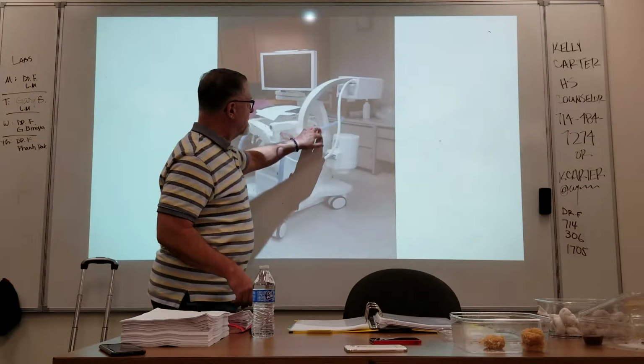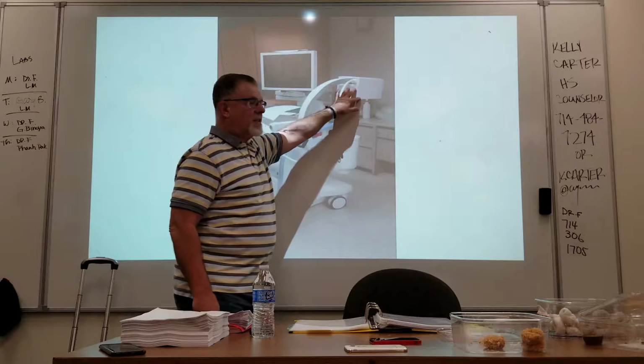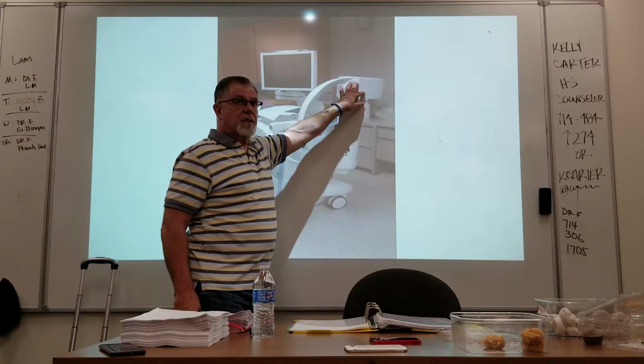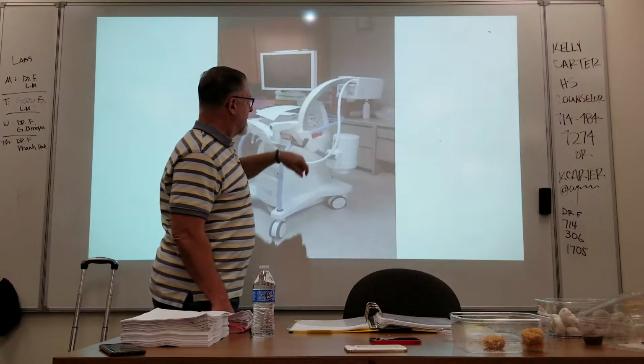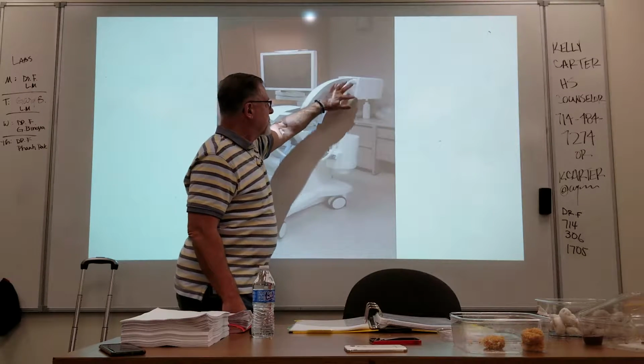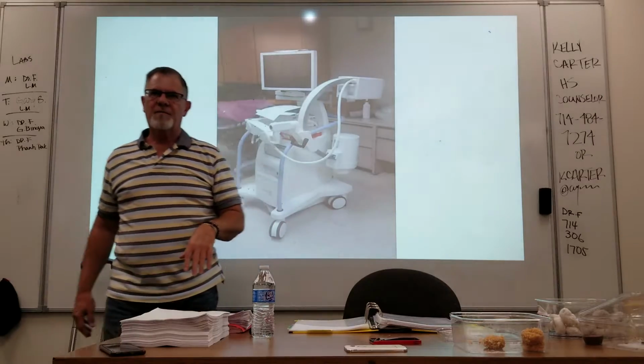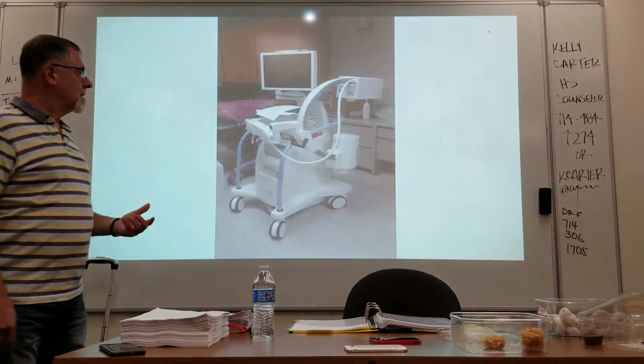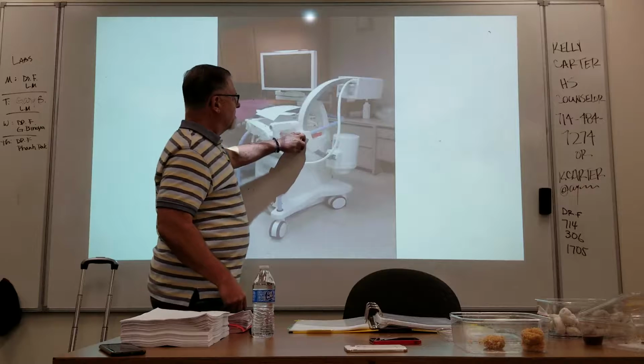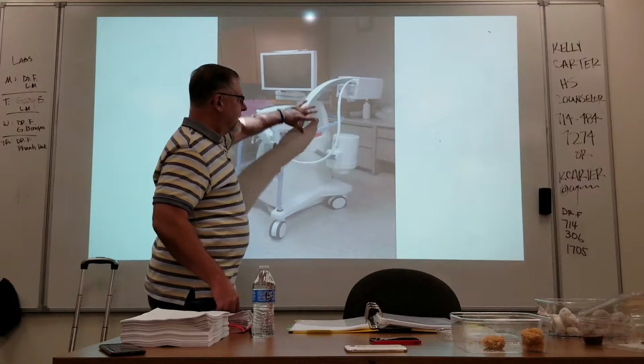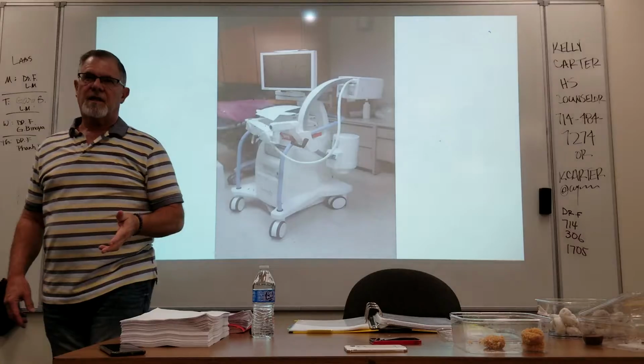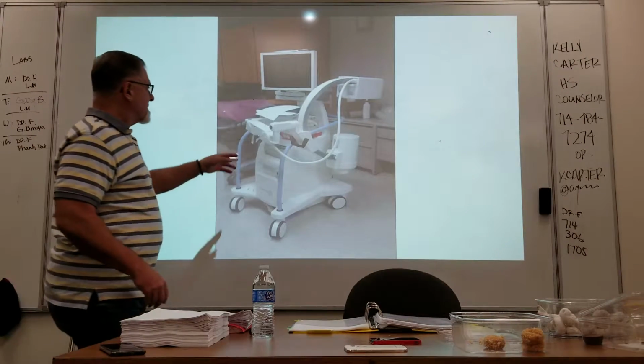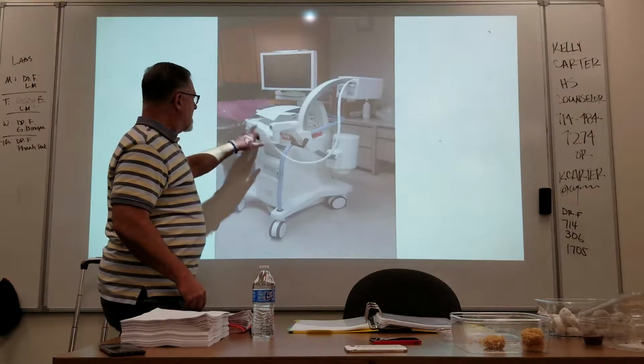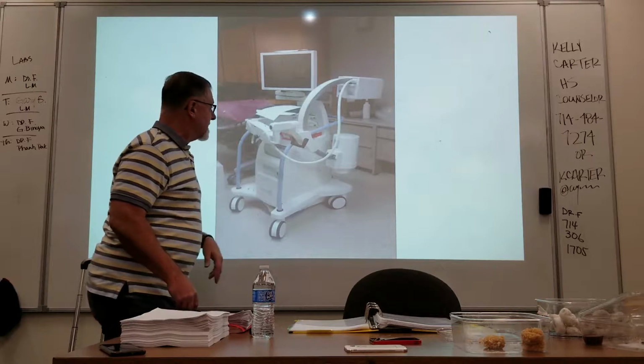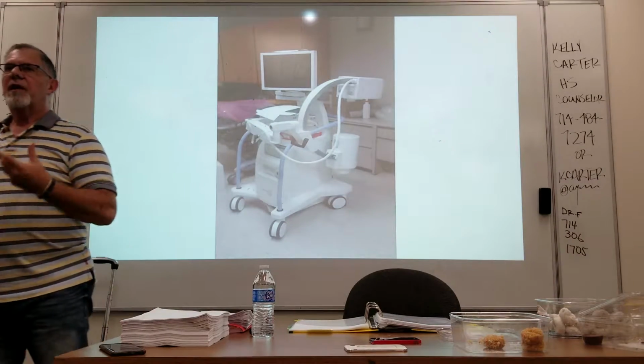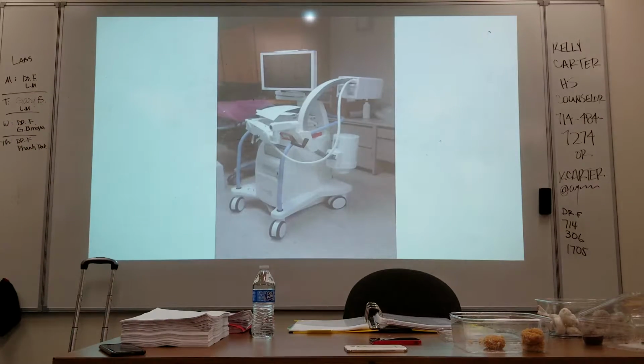For example, on this unit, the X-ray tube head, the generator is actually partially up here because it's digital, it's electronic. So the difference in weight between this and this is extreme, and there is no counterweight on it. So when you let this go, if it's not in a nice balanced position, it's going to swing to where the weight is. So you have to watch that. Same thing for these arms. Again, these are all manual locks on these articulating arms. You need to be very careful when you unlock that it's not just going to flop.